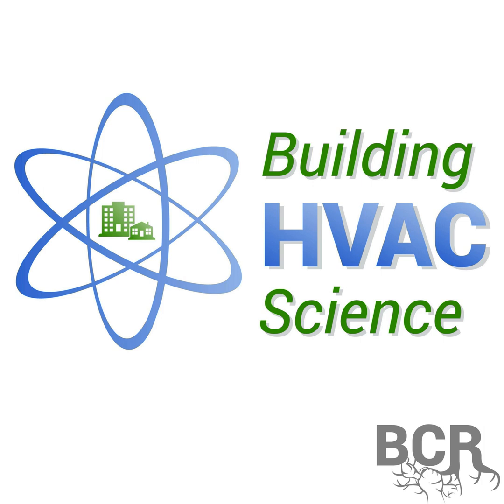How about in terms of the need for it to operate and what it does? It has sensors built into it, and how do they work? Yes, so as a smart ventilator, we are monitoring carbon dioxide and total VOCs, 2 separate sensors, and from our view, 2 essential sensors for managing air quality. And if either one of those gets above an occupant designated set point, so for example, my house, which you can see live data for the past 4 to 5 years online from our website, I keep the set point at 850 parts per million. And if we go above that threshold, the unit goes into fresh air mode and brings it down about 100 ppm below that threshold. And so basically it's looking at either one of those 2.